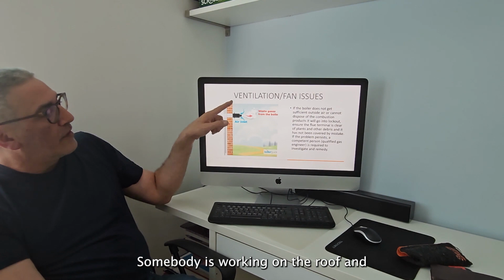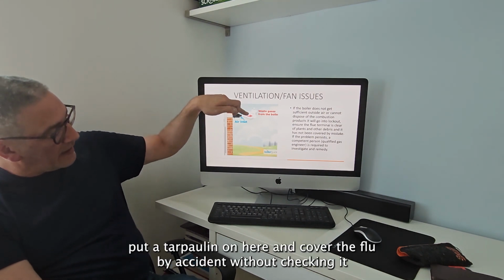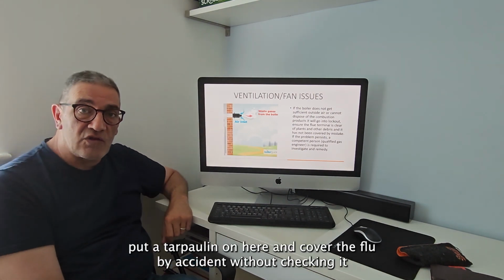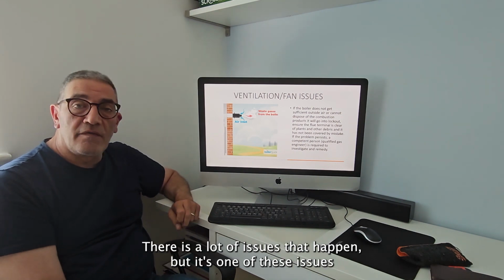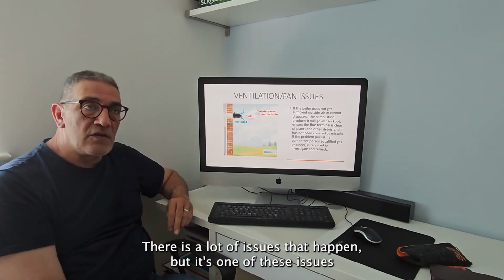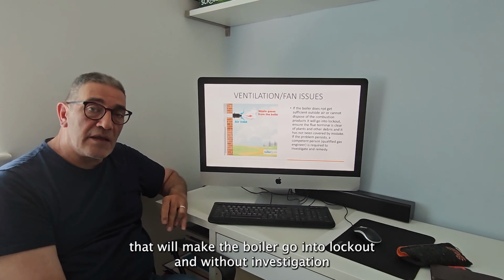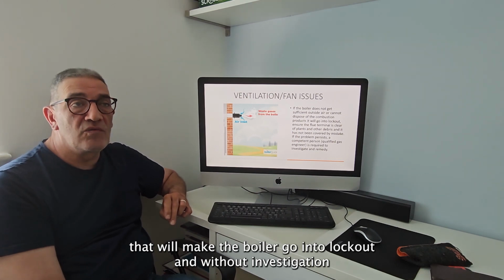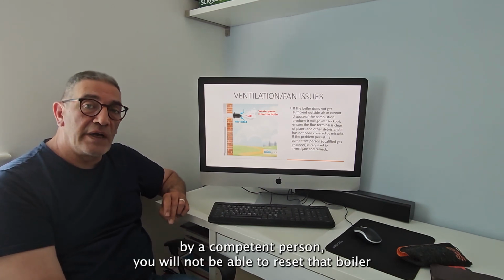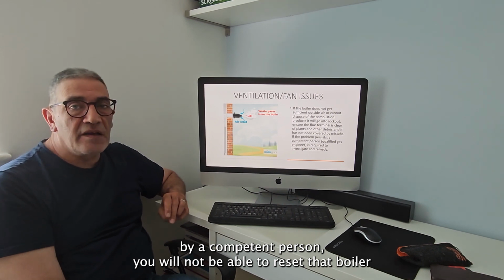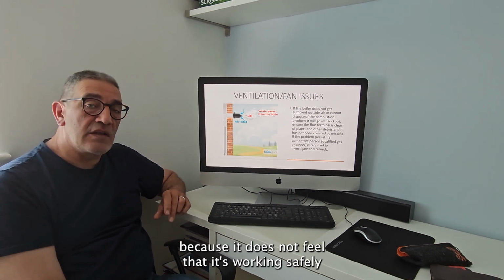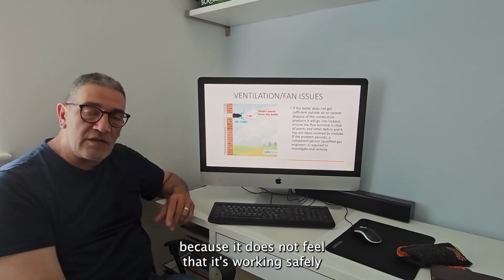Somebody is working on the roof and put a tarpaulin on here and covered the flue by accident without checking it. There are a lot of issues that happen, but it's one of these issues that will make the boiler go into lockout, and without investigation by a competent person, you would not be able to reset that boiler because it does not feel that it's working safely.